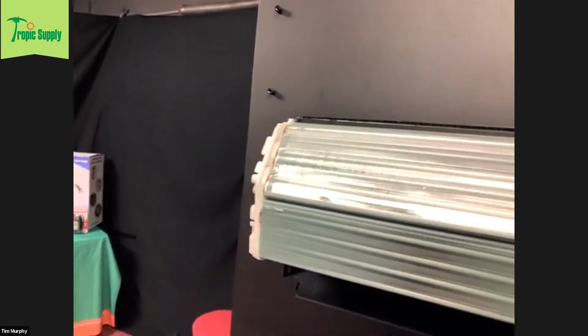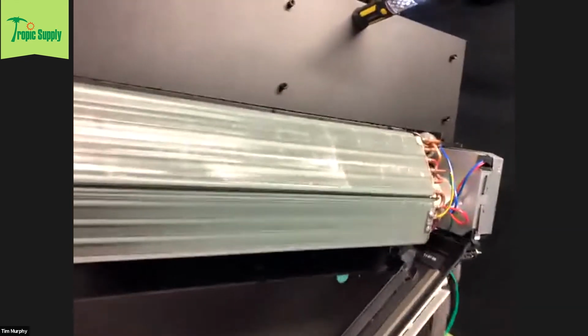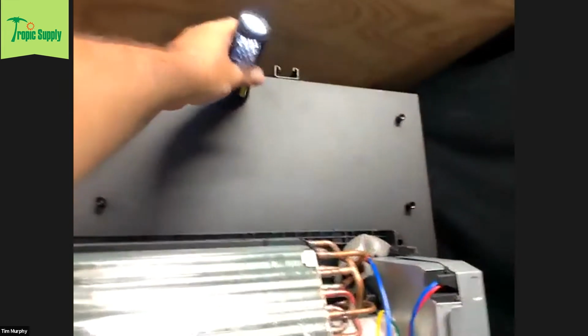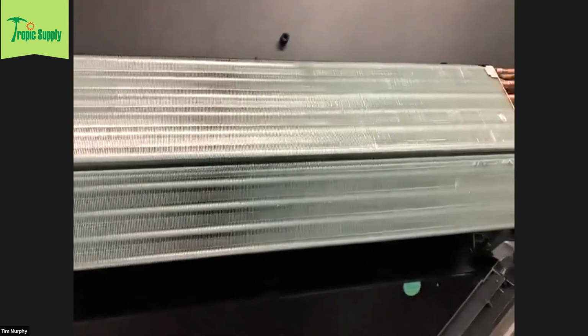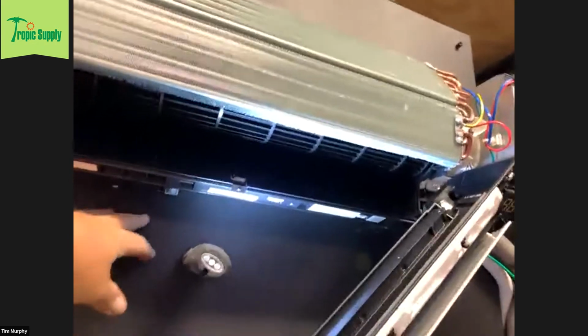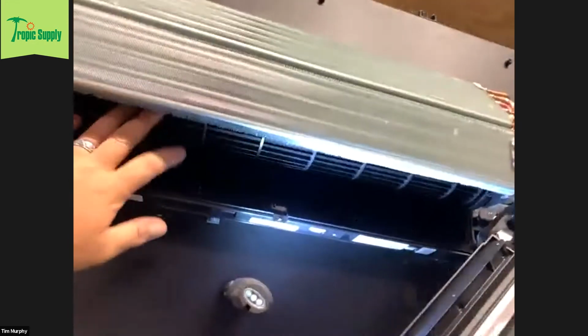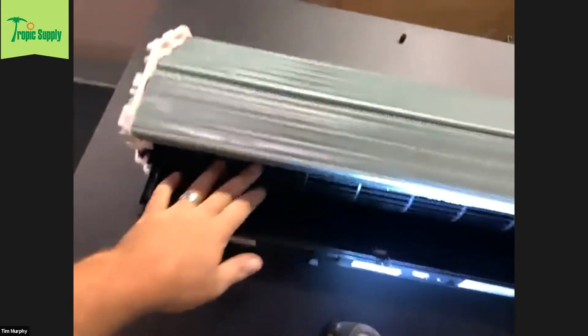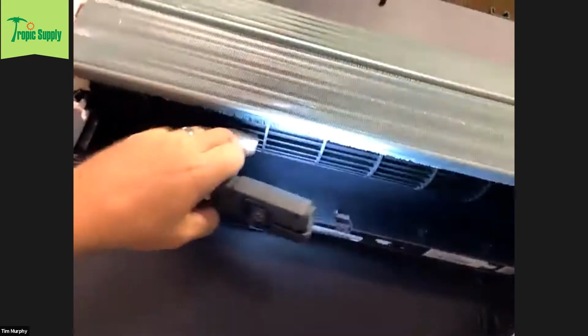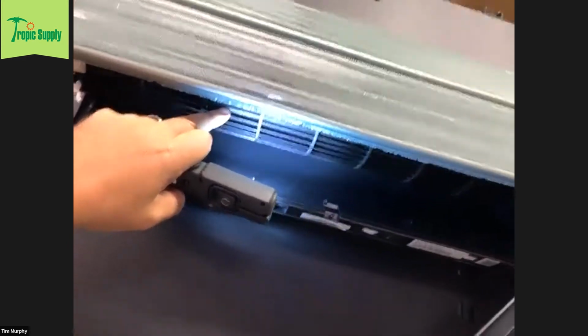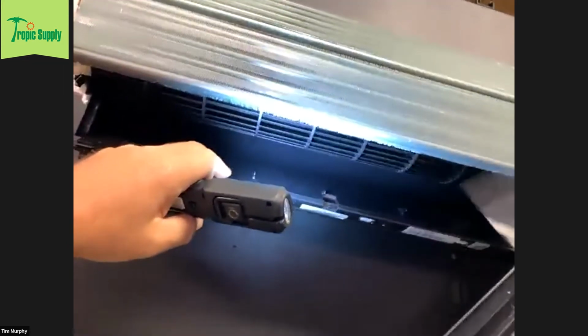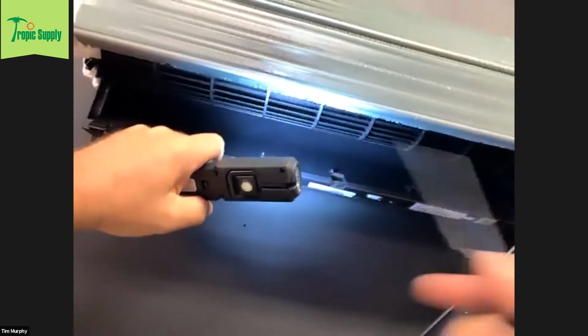Another recommendation for a deep clean on these systems is to remove the blower wheel, which I'll show you now. I've seen a lot of companies, and even my own guys in the field, think removing the blower wheel is a pain since these get clogged with dirt and the turning vanes are close together. So instead they just hose it off or use a pressure cleaner in place.